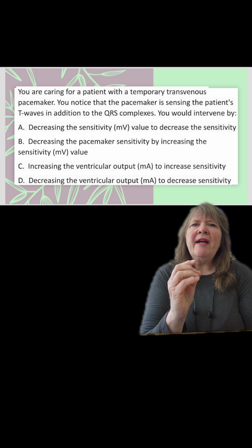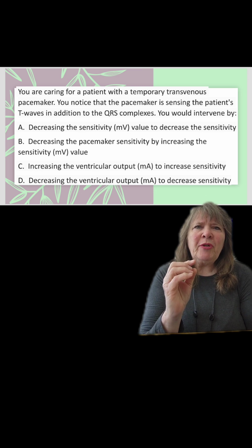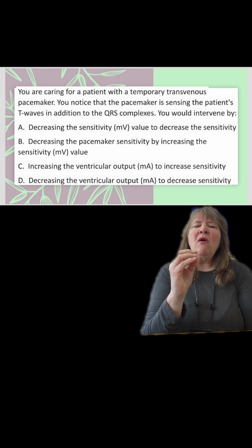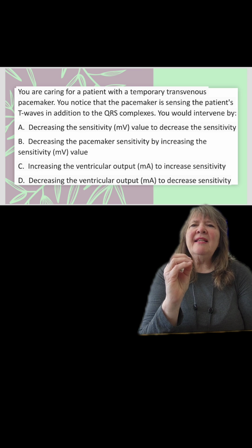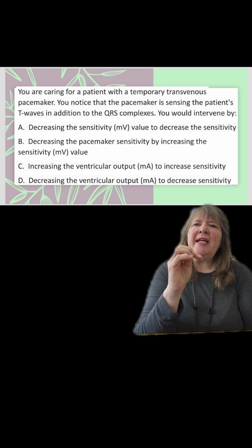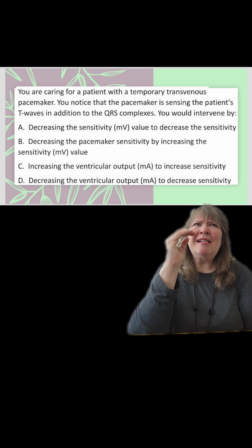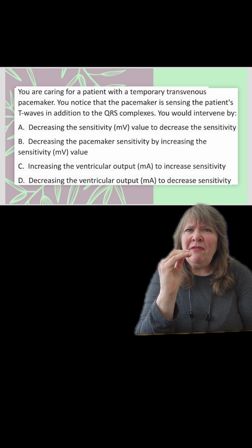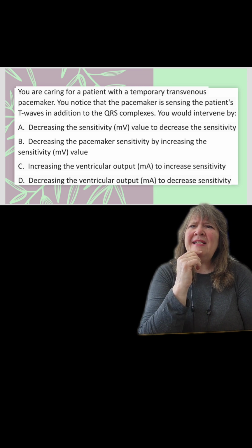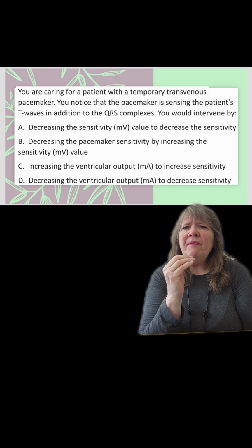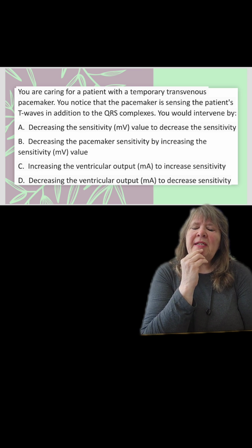Now, here's where it gets a little bit tricky. When we decrease the sensitivity, we are basically wanting to increase the sensitivity value. Now that sounds weird, doesn't it? You want to make the pacemaker less sensitive, and so you increase the sensitivity or millivolt value. Well, let's think about this for a second.